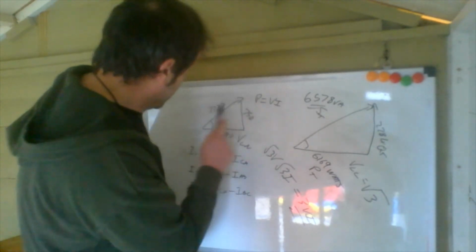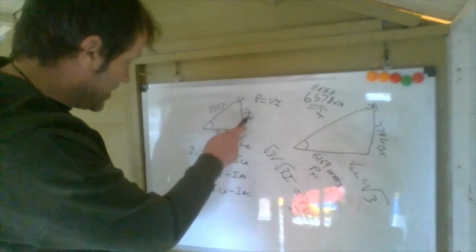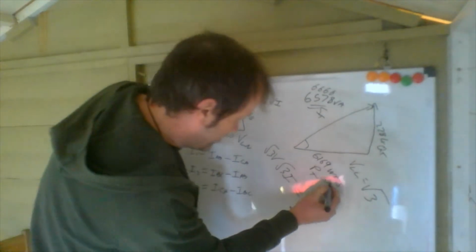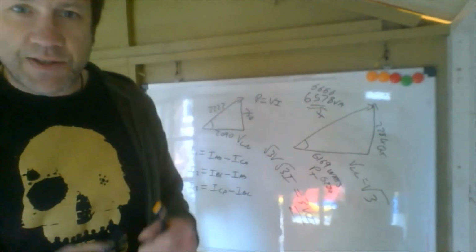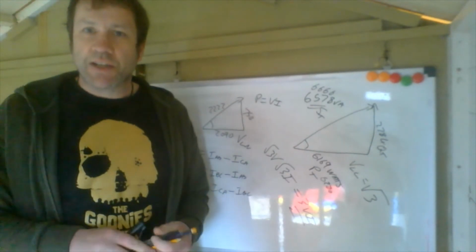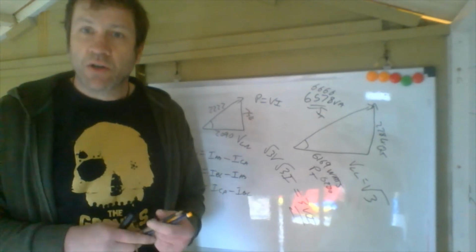So looking at that, 2222, multiply that by 3, and you're not far off. That should be something like 6666. So it's pretty close. It's just my workings. And again here, 754 times 3, just about there, and 2090 times 3, that would be 6180, I think. No, 6270 in fact. So you can see there that the delta differs. It uses line to line voltage, which means it's got higher power consumption and higher current drawn in.